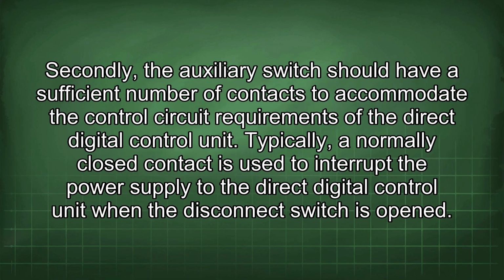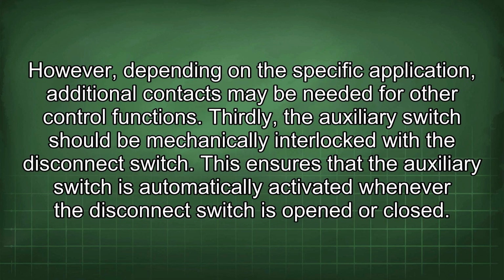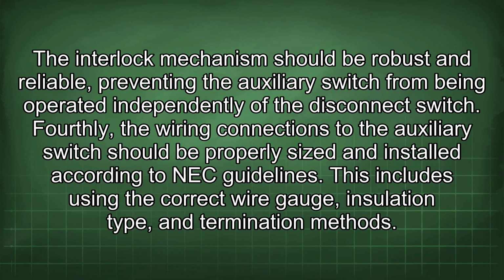Secondly, the auxiliary switch should have a sufficient number of contacts to accommodate the control circuit requirement of the direct digital control unit. Typically, a normally closed contact is used to interrupt the power supply to the direct digital control unit when the disconnect switch is opened. However, depending on the specific application, additional contacts may be needed for other control functions. Thirdly, the auxiliary switch should be mechanically interlocked with the disconnect switch. This ensures that the auxiliary switch is automatically activated whenever the disconnect switch is opened or closed. The interlock mechanism should be robust and reliable, preventing the auxiliary switch from being operated independently of the disconnect switch.